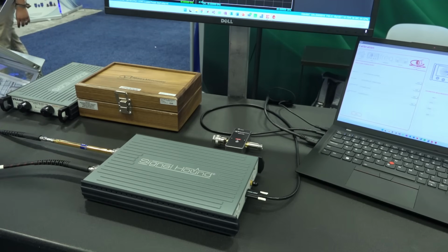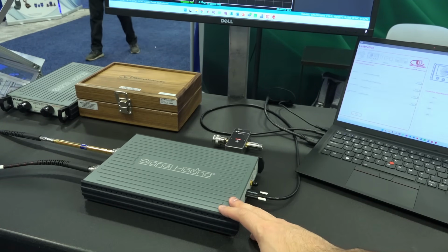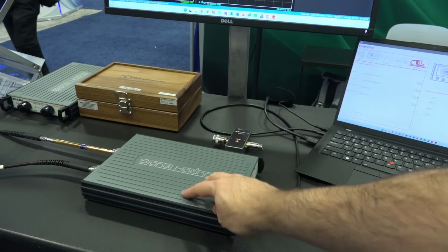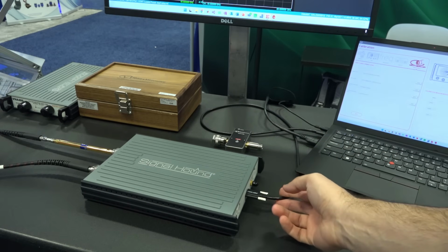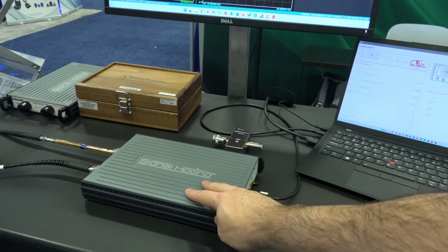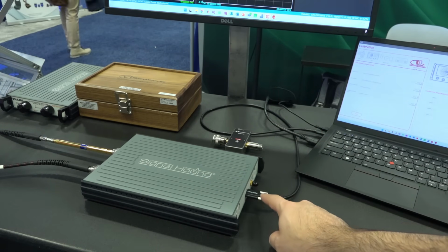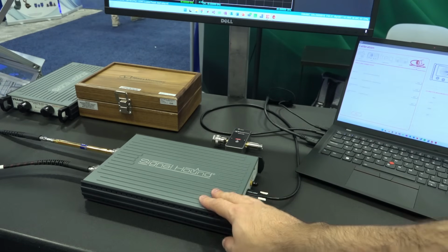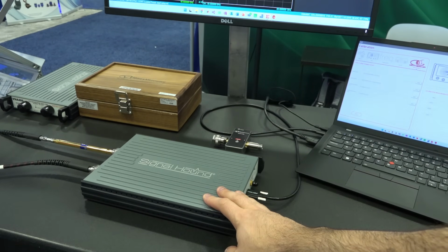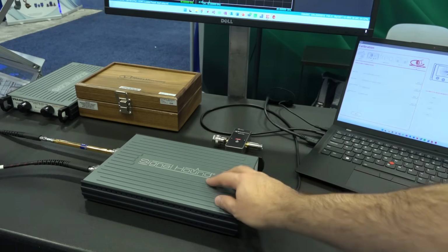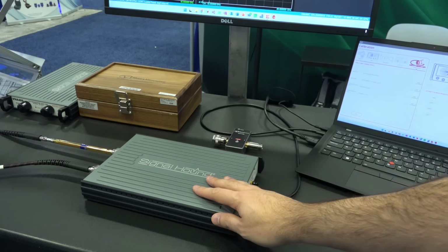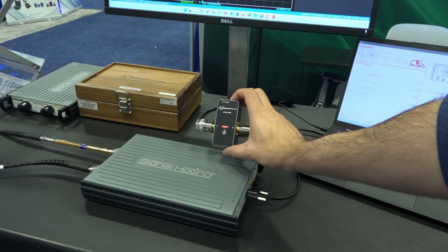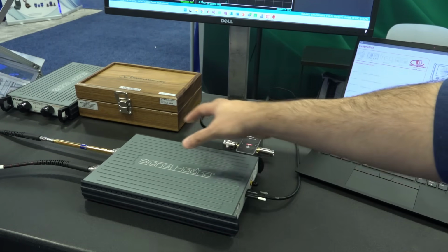So now, building on the same philosophy of portability that Signal Hound has, here we have a 40 megahertz to 40 gigahertz two-port network analyzer that is entirely powered from a single USB port. I don't think I've ever seen a system that can run from a single USB port and cover this kind of frequency range, with 132 dB of dynamic range. It supports all the programming interfaces like SCPI. It supports all the mechanical cal kits. It's completely open for that. And it also has a variety of eCal modules, this one from Maury, that you can use to do this.